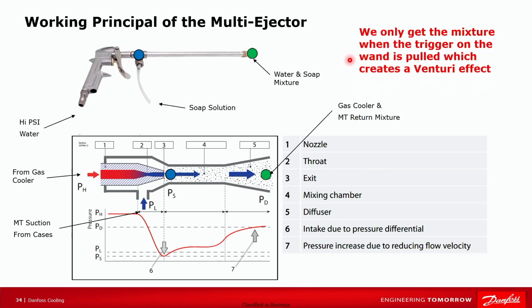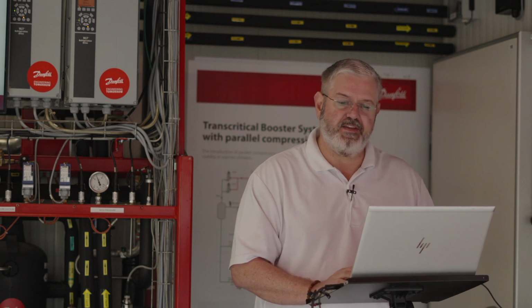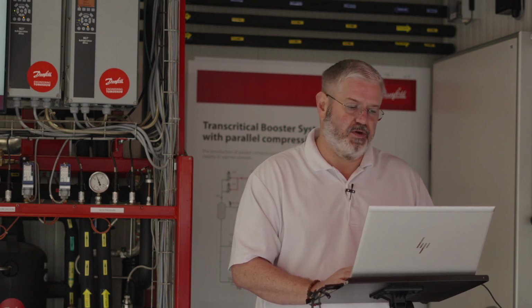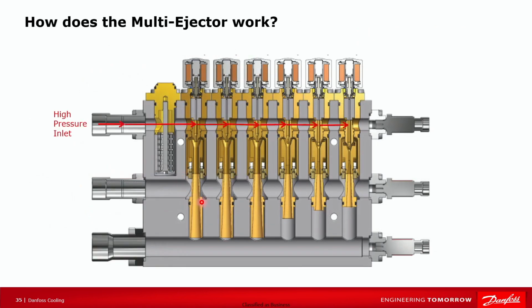One thing to note is that, similar to parallel compression, you're only going to get this effect when you're in high ambient conditions. So having said that, think of the ejector working when you've pulled the wand with the trigger on the pressure washer wand. We only get that Venturi effect when we've pulled the trigger. So that Venturi effect goes something like this.